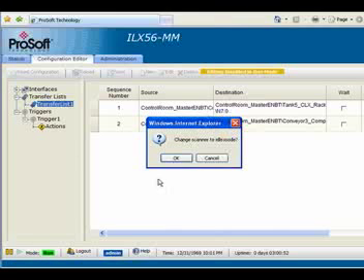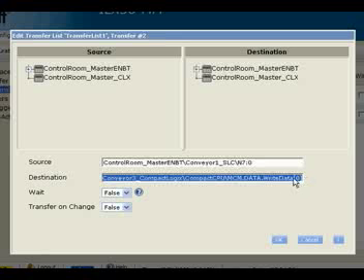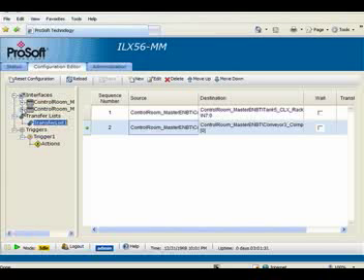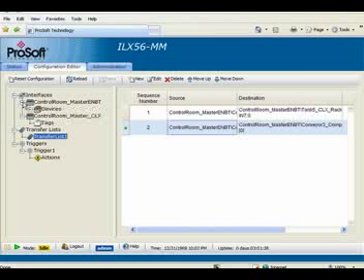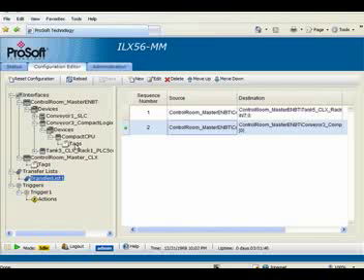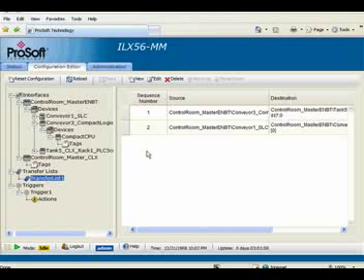I have a good idea of why it's erroring out, so let's go back to configuration — first I need to put it in idle mode. I'll select the appropriate transfer, and I believe that WriteData tag is a read-only tag. Let's open up the tags for the CompactLogix — drill down to the devices under Ethernet, expand it, and look at the tags. Notice the read-only attribute — that means you can't write into that tag. So I'll go ahead and delete this transfer so we can see that the module runs without error. I'll click Delete, then OK.